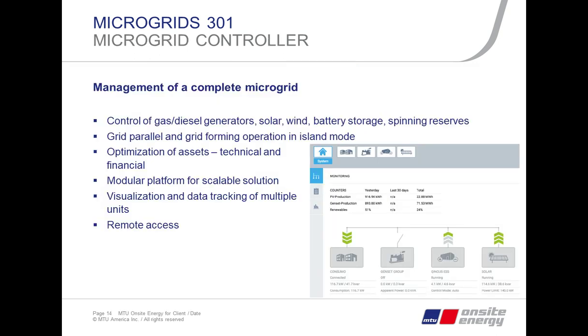On a high level, what does a microgrid controller do? It manages the complete microgrid, controls the gas and/or diesel generators which we typically have, and there's a solar, wind, battery storage, spinning reserves component to it. So all those additional resources we have, we have to control all of these. It may or may not be grid parallel or island mode, or can be both.